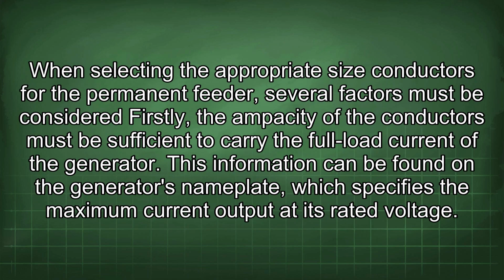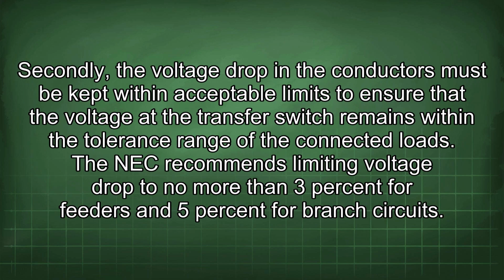When selecting the appropriate size conductors for the permanent feeder, several factors must be considered. Firstly, the ampacity of the conductors must be sufficient to carry the full load current of the generator. This information can be found on the generator's nameplate, which specifies the maximum current output at its rated voltage. Secondly, the voltage drop in the conductors must be kept within acceptable limits to ensure that the voltage at the transfer switch remains within the tolerance range of the connected loads.